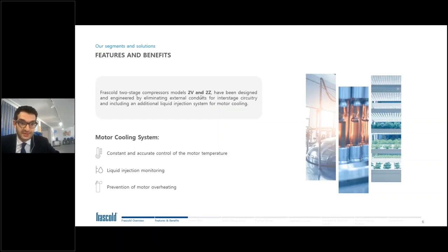Two-stage compressors, our models 2V and 2Z, are designed and engineered by eliminating external conduits. So if you look at the two-stage compressor, it seems almost a standard compressor. You just notice a different position of the valves. We will see better later. There are no external conduits for the interstage, unlike the big majority of two-stage compressors available on the market.